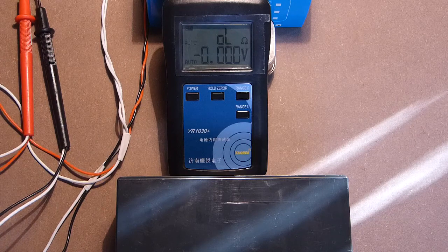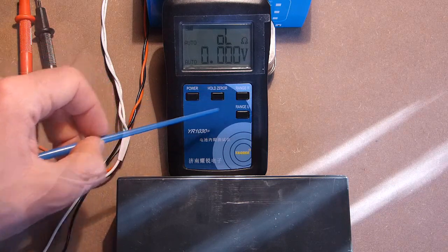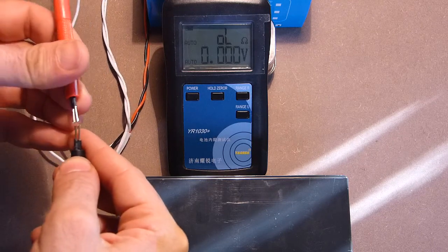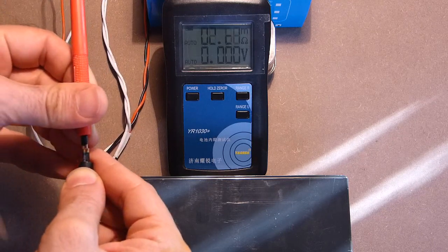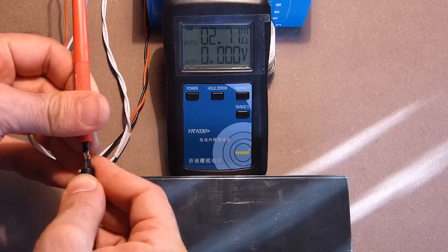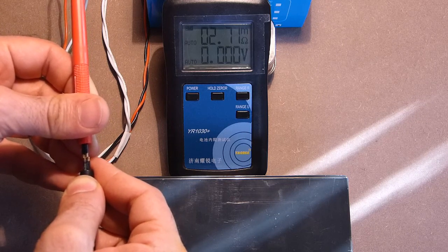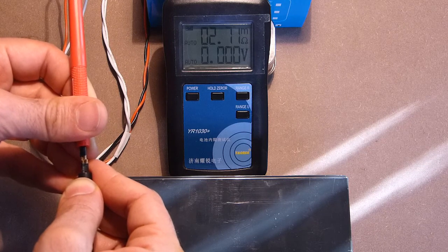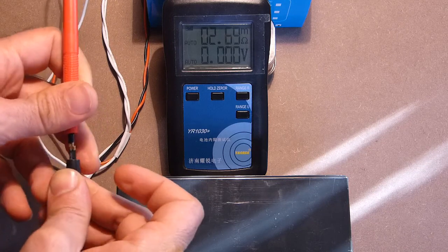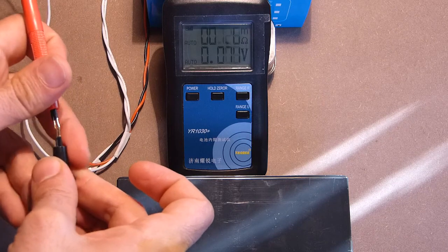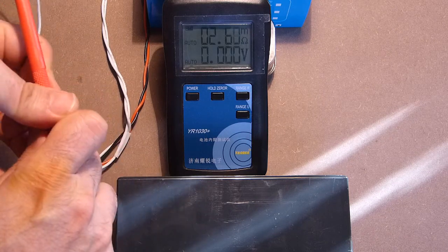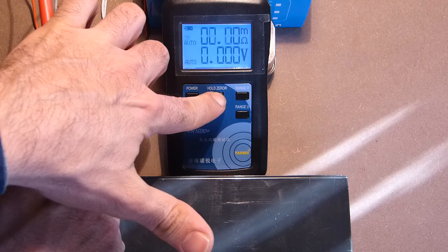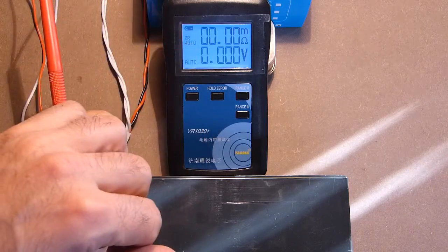If you are not satisfied with the indication after getting this device, you can calibrate it. You should connect the plus probe to the minus probe and press the 0 button, this way. Here the accuracy is 2.7 milliohms. Now I have 0.